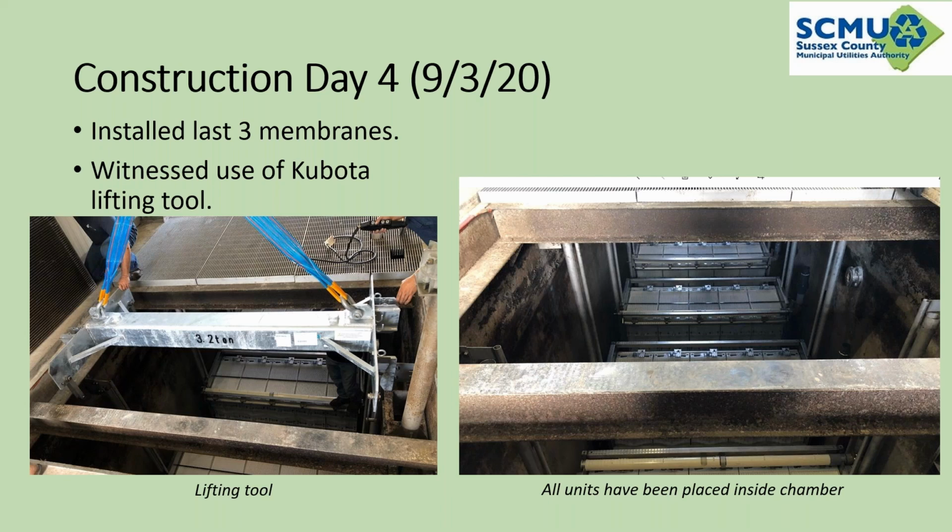And this is one of the real big things. We witnessed the use of the Kubota lifting tool. One of the operational and maintenance things we talked about was having a single pick point. That ended up not being feasible. We also talked about keeping that pick point above the water line. Unfortunately, that wasn't feasible either for either manufacturer.